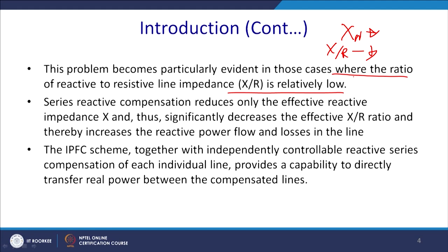This is the limitation of impedance-mode series compensation. When injecting XQ, you subtract from XL, so the X/R ratio gets reduced. This problem becomes particularly evident where the ratio of reactive to resistive impedance is quite low due to XQ injection. Series reactive compensation reduces only the effective reactive impedance X, significantly decreasing the effective X/R ratio and thereby increasing reactive power flow and losses in the line, since I-squared losses will increase.